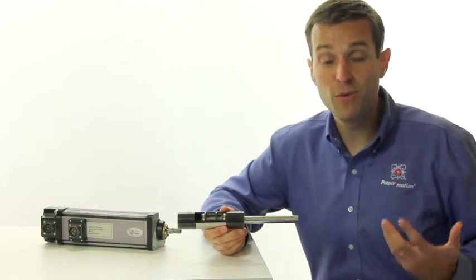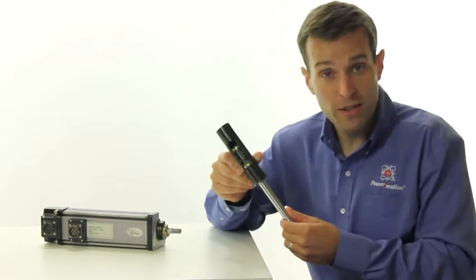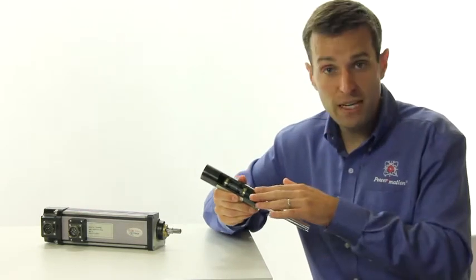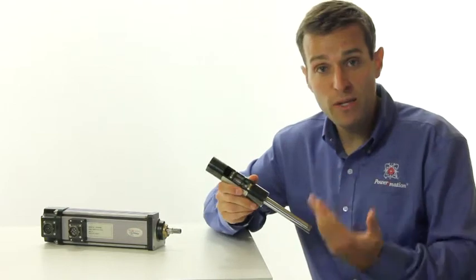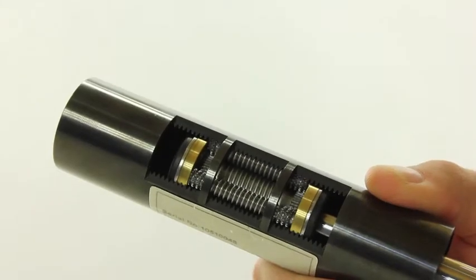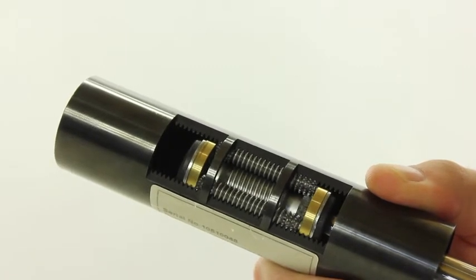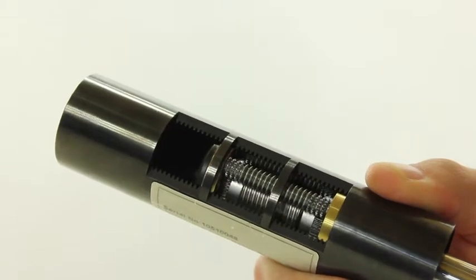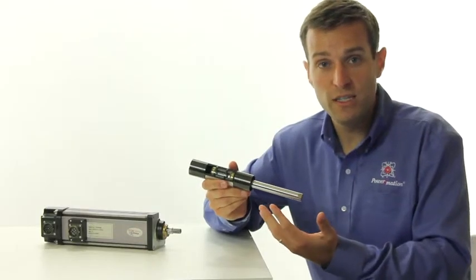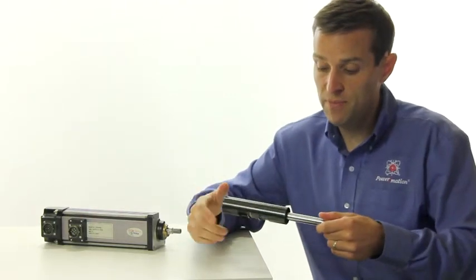At the heart of every roller screw actuator is a roller screw mechanism, and here it is right here. I've got this black tube and I've got this rod, and in between the rod and the tube are a series of planetary rollers. They provide the interface between the two devices to minimize the friction and also transfer the rotational motion into linear motion. You can see as I spin the tube, the rod will advance.